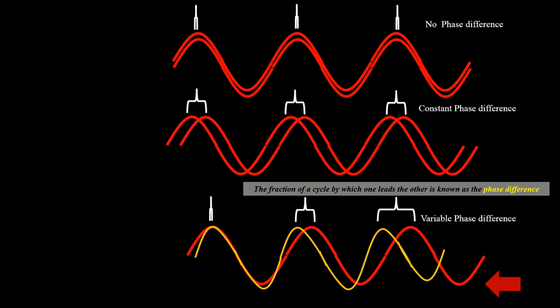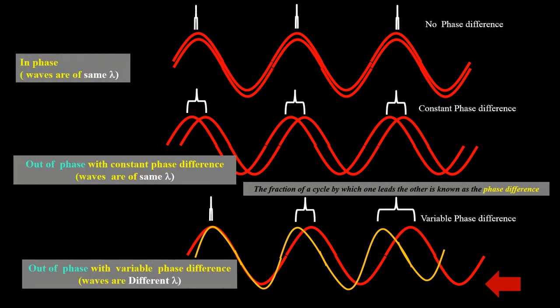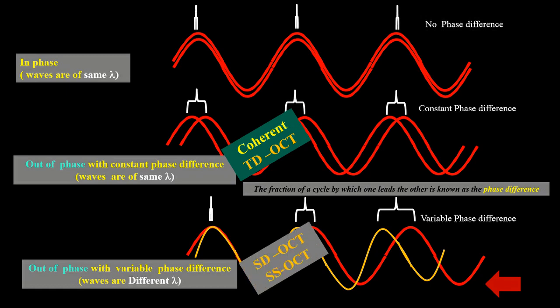In the top diagram there is no phase difference. In the middle part we have a constant phase difference, and at the bottom we have a variable phase difference. The first represents rays in phase of the same wavelength. The middle represents coherent light — out of phase but with a constant phase difference and the same wavelength — and this is used in time domain OCT. The bottom represents out-of-phase rays with variable phase difference made of different wavelengths, and this is used in spectral domain or swept source OCT.